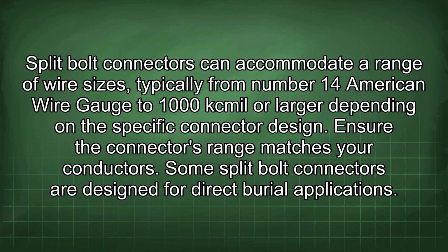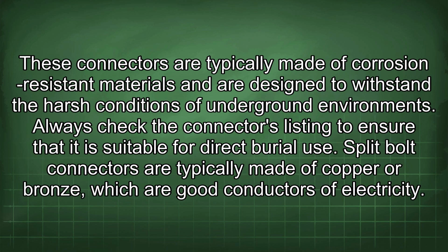Split bolt connectors can accommodate a range of wire sizes, typically from number 14 American wire gauge to 1000 kcmil or larger, depending on the specific connector design. Ensure the connector's range matches your conductors. Some split bolt connectors are designed for direct burial applications. These connectors are typically made of corrosion-resistant materials and are designed to withstand the harsh conditions of underground environments. Always check the connector's listing to ensure that it is suitable for direct burial use.